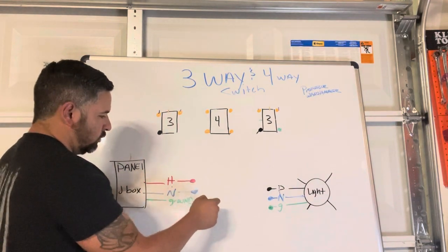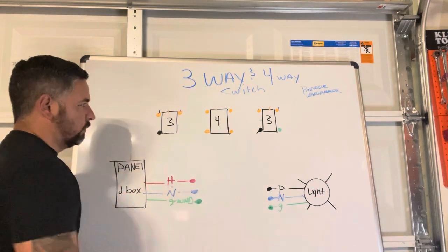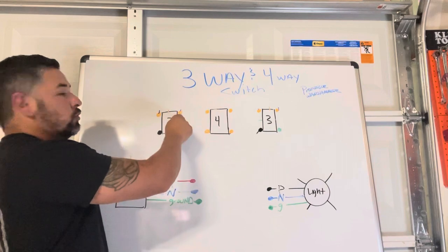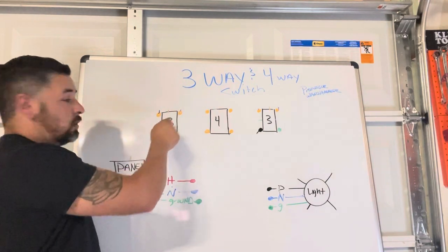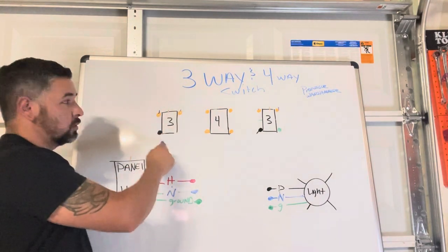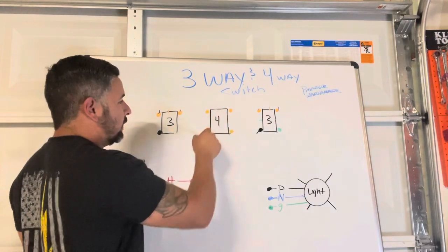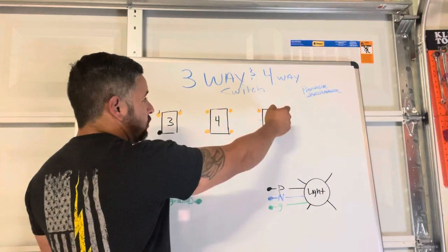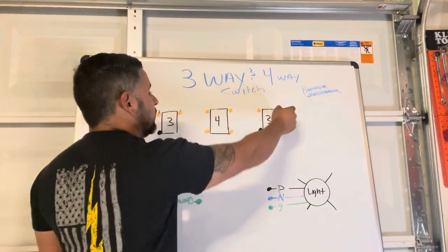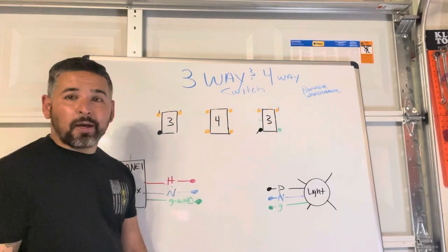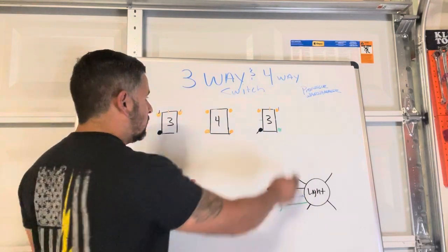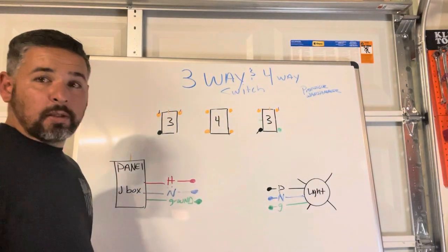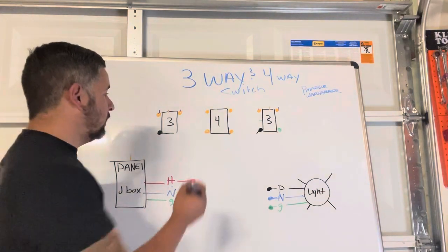Over here on the panel side it's gonna be red, blue, green: hot, neutral, ground. On your three-ways you're gonna have two gold screws, one black screw. On a four-way you're gonna have two gold on top, two gold on bottom. On your three-way you're gonna have two gold on top, black on bottom. All of them are gonna have grounds, so the grounds are for everything.